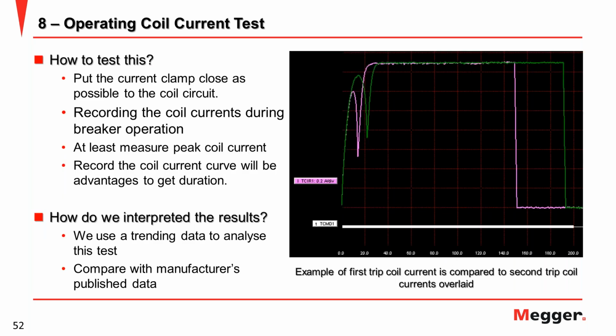This example shows two comparisons between coil current before and after. So the first test and the second test give you information about the difference between the first peak and second peak. So if you have a different coil current, it gives you a different breaker timing operation, whereas the green curve gives you the longest timing compared to this purple curve.